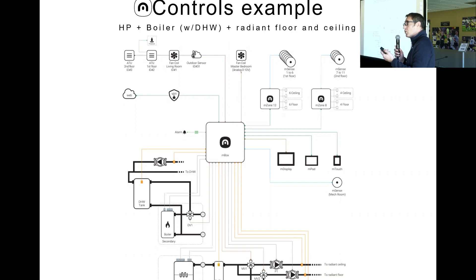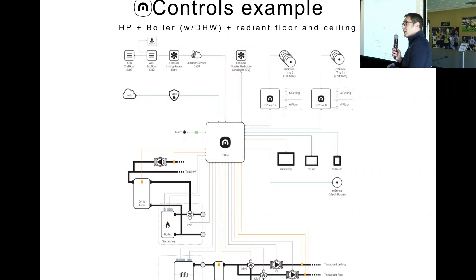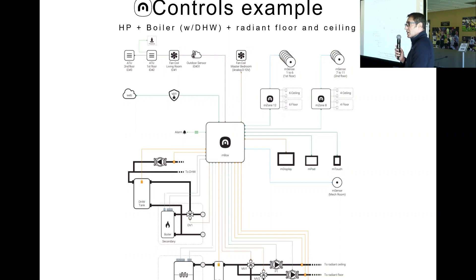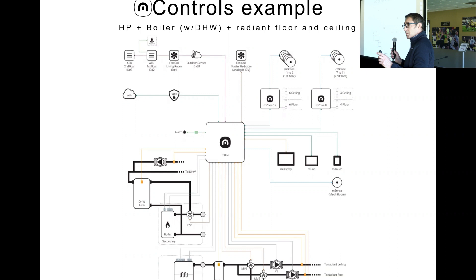If we are doing radiant cooling on the ceiling, we definitely want to go more aggressive than on the floor, because if we are aggressive on the floor and people walk into a room, the floor is cold, there are many people, and the humidity goes up — we can cause a disaster, like condensation. So we keep them on different hydronic loops with two different logics and two different temperatures.